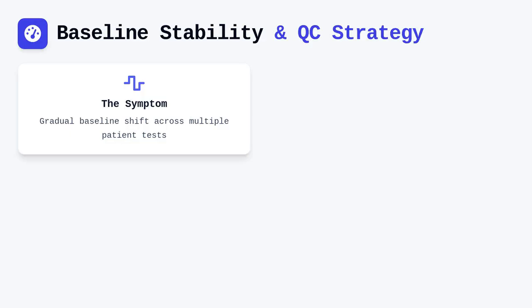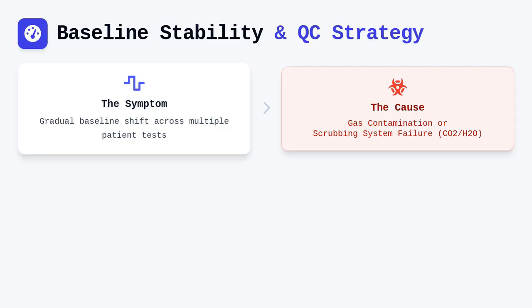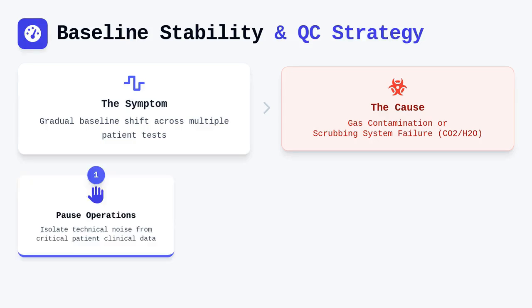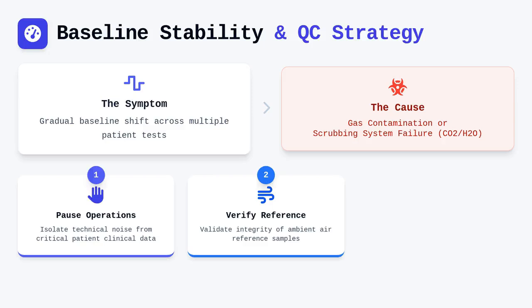Baseline stability is another critical dimension of your quality control strategy, particularly when dealing with gas analyzers and sensors. If you notice a gradual shift in the baseline that persists across multiple patient tests, you are likely looking at gas contamination or a failure in the scrubbing system that removes CO2 or water vapor. Whenever these deviations occur, you must pause operations and verify the integrity of the ambient air reference samples before attempting any further diagnostic procedures.